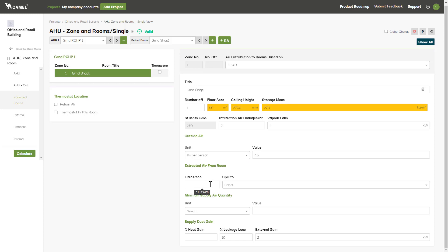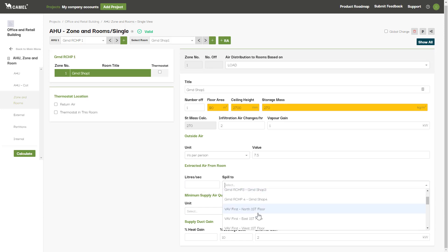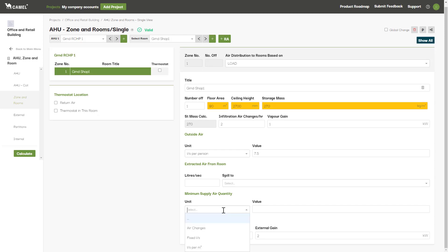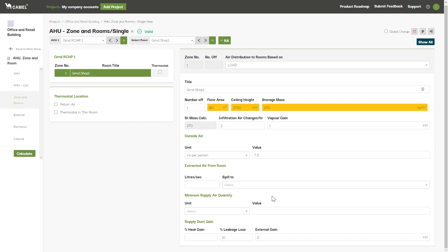Here you have the option to extract air from the room and spill it to another room in the project. You can also specify a minimum supply air quantity for the room. Be careful not to set this too high, particularly for rooms with low loads, as it could result in a high cooling coil leaving air temperature for this AHU.